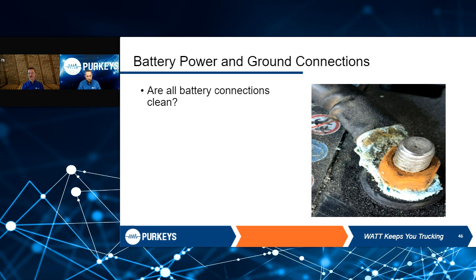And of course, you got the green fuzz. You always watch out for the green fuzz, any oxidation or corrosion on those battery terminals. That's going to greatly impact current carrying capacity of that connection. Keeping these cleaned off, sometimes spraying some kind of a corrosion protectant over that connection after it's been made, all things to help with this.